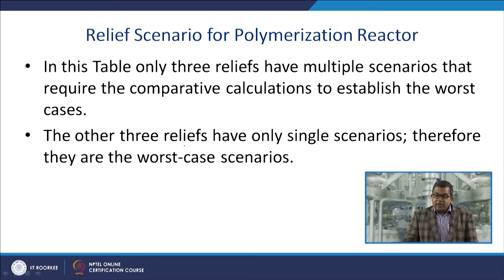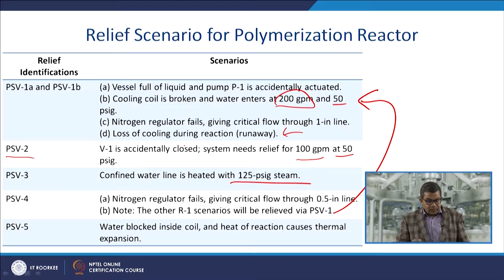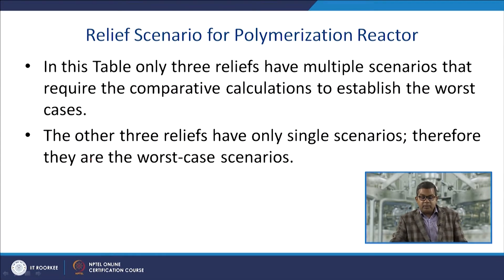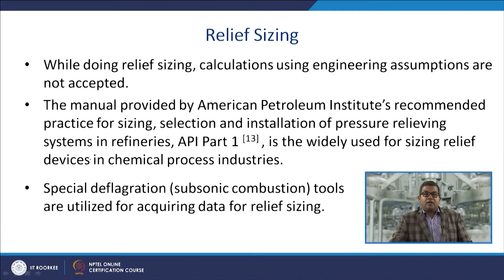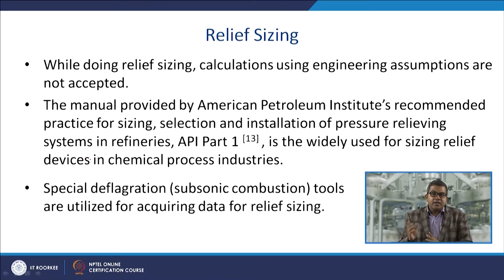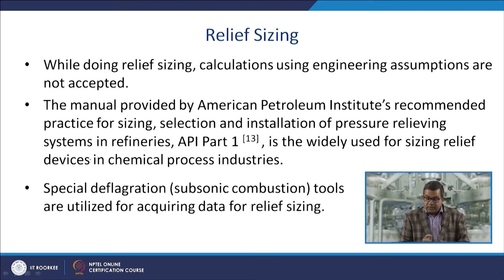In this relief scenario table, only three reliefs have multiple scenarios requiring comparative calculations to establish the worst case, while the other three reliefs have only a single scenario and are therefore also the worst case. Engineering assumptions alone are not accepted for relief sizing calculations. The API Recommended Practice for sizing, selection, and installation of pressure relieving systems is widely used in chemical process industries.